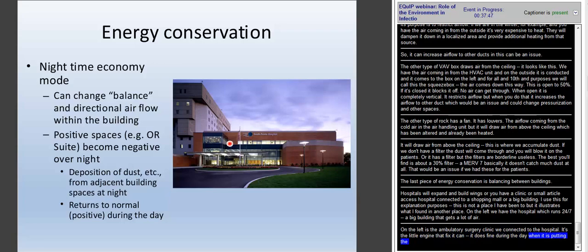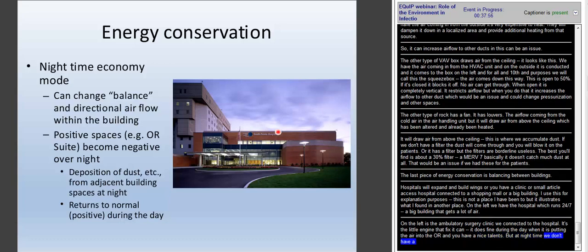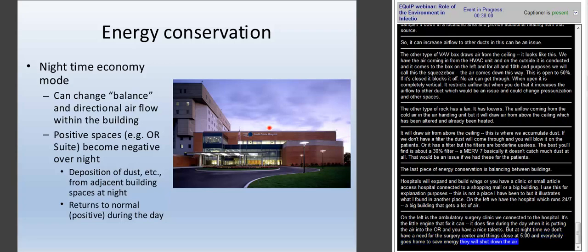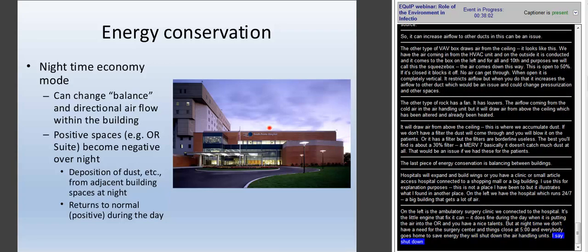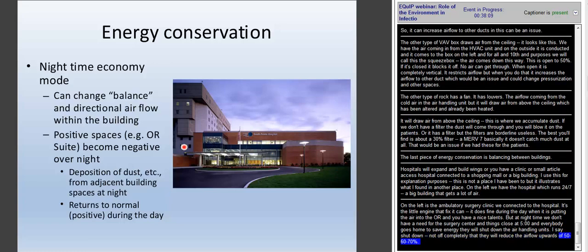But come nighttime, when we don't have a need for the surgery center and things close down at 5 o'clock and everybody goes home, to save energy, they will shut down the air handling units. Now, I say shut down, not exclusively off completely, but they will reduce the airflow upwards of 50 to maybe even 60 to 70%. And by doing that, this little engine that could is no longer balanced off here with the hospital. The hospital is now pumping air into here.